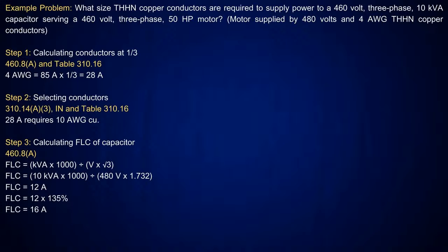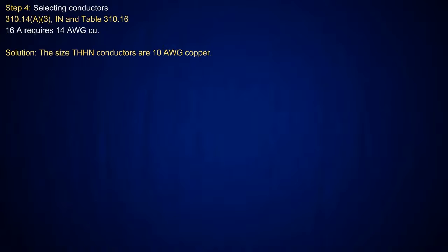Now, also in 460.8(A), I'm going to be calculating the full load current of the capacitor. It's just like doing a transformer, generator, or anything else. I need to get the kVA of the capacitor, take it at 1,000, then divide it by the voltage. In this case, I have 480 volts times 1.732 for the three-phase, which gives me 831 volts, divided into that 10,000, and that's going to give you 12 amps. But it tells you there that you also have to take it at 135%, which gives me 16 amps. Now, as you go in the second part of it, 16 amps is going to require number 14. But you have to use the largest between the two.